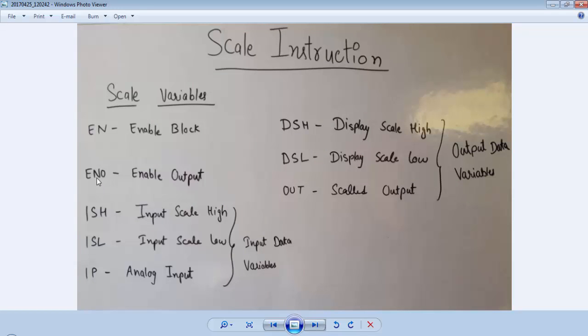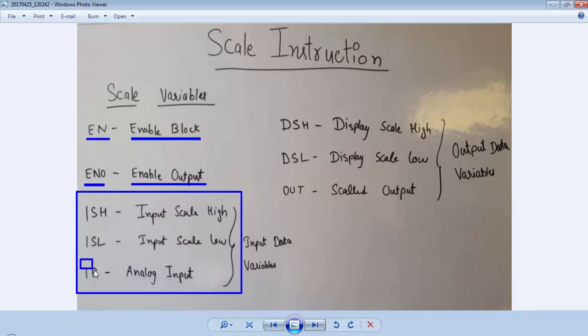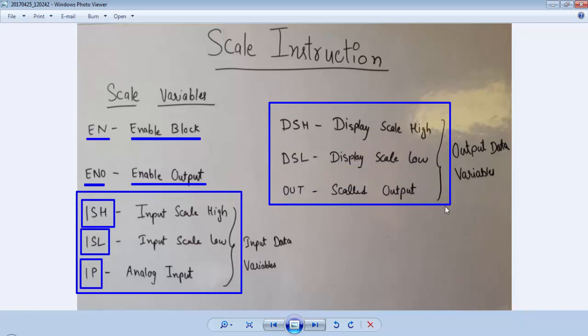These are the variables for a scale instruction. First is Enable — whenever the enable signal is high, the scale instruction block is enabled for calculation. ENO is enable output; whenever the result is greater than 0 it activates the ENO pin. IP is the analog input channel. ISL is the input scaling low value and ISH is the input scale high value. Out stores the scaled output, DSL is the display scale low value, and DSH is the display scale high value.